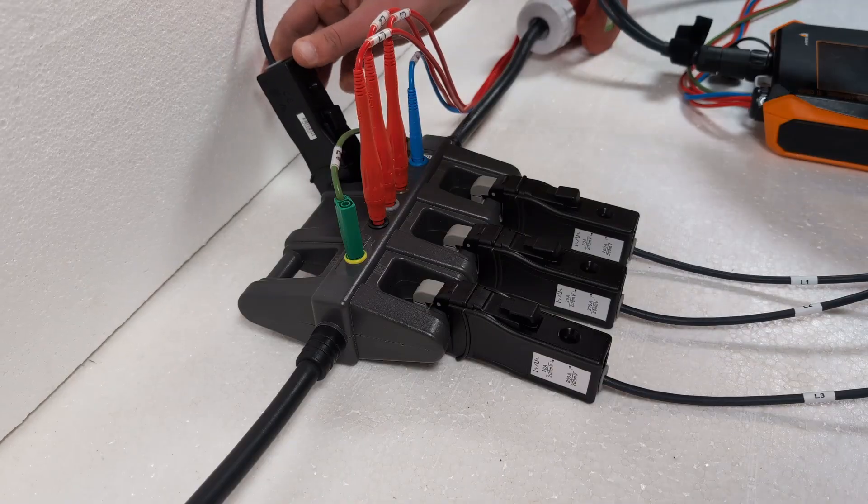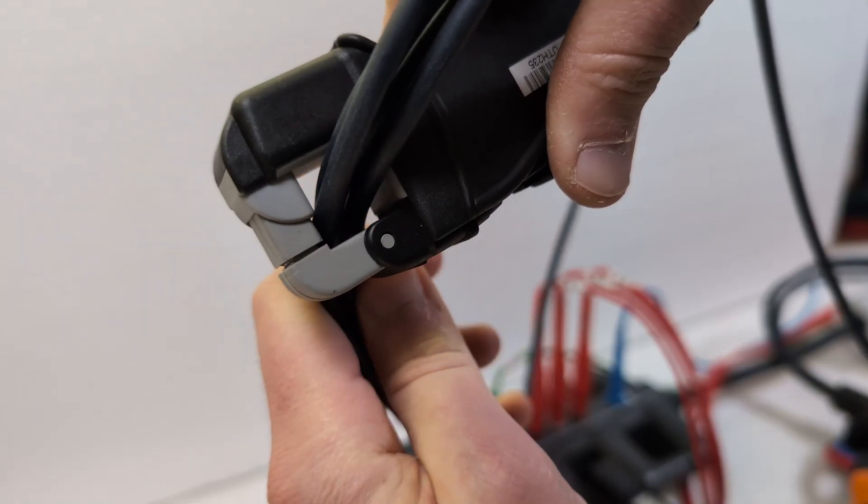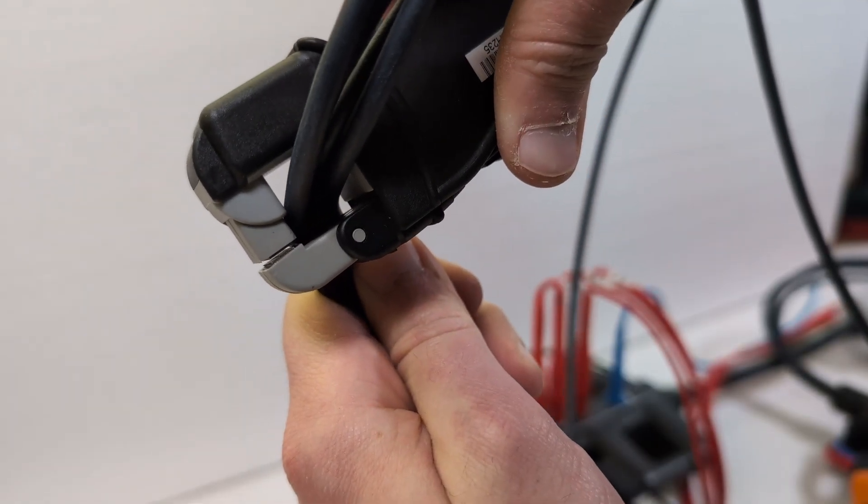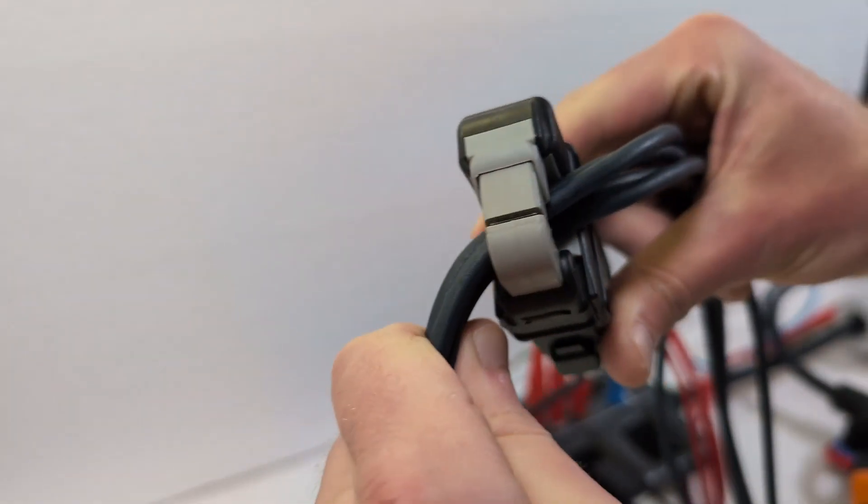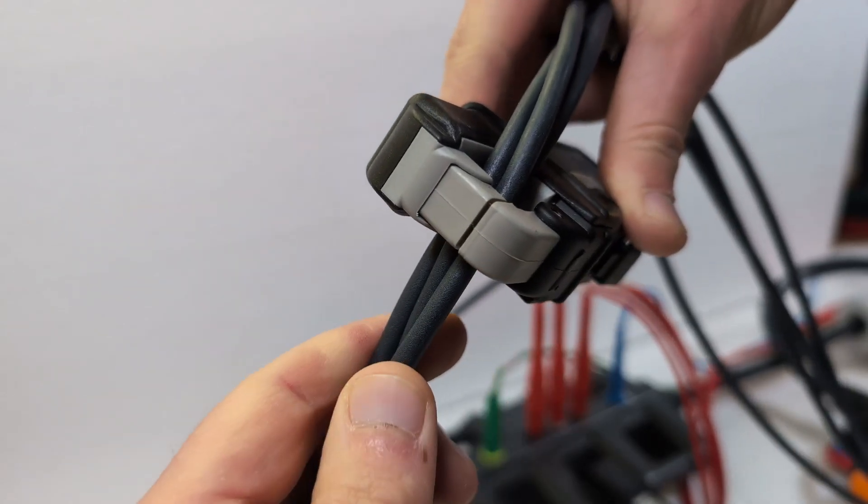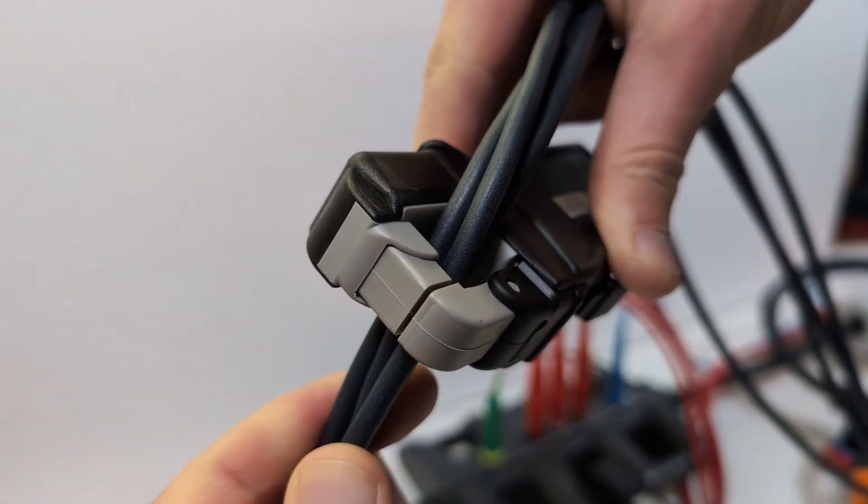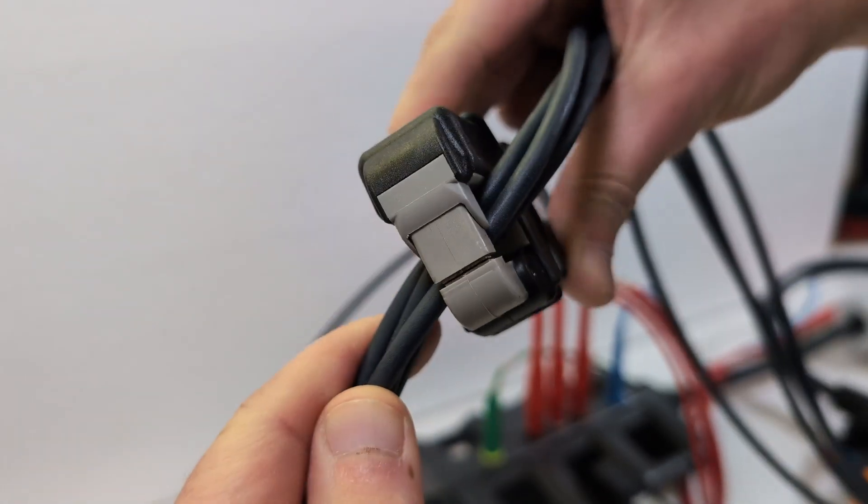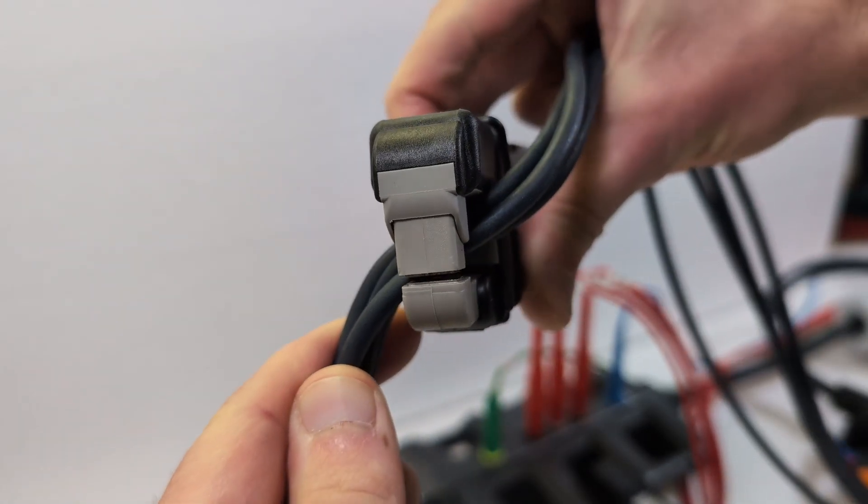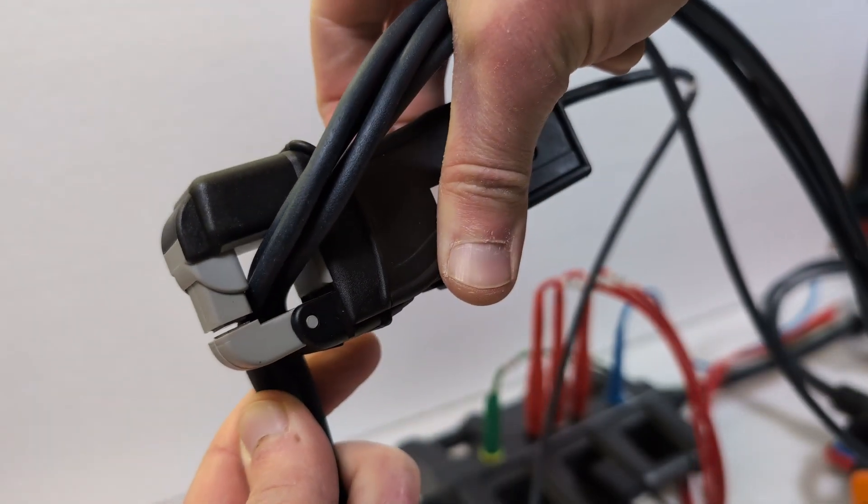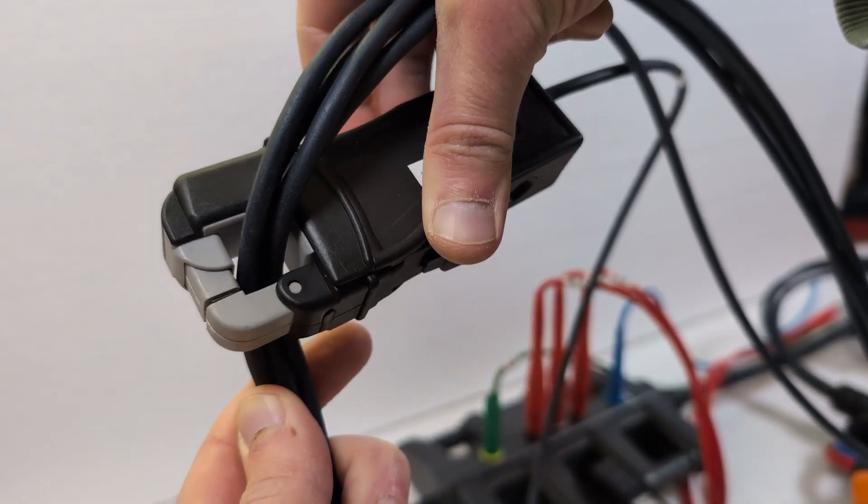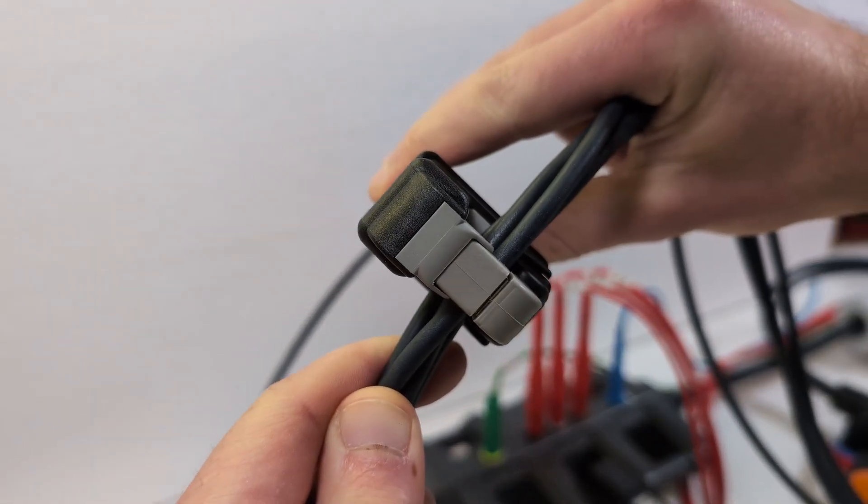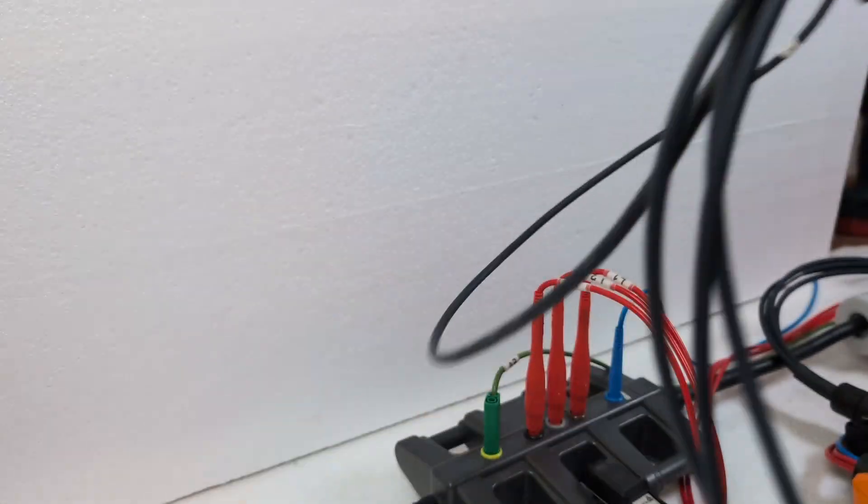Even if there is not much space available, you should ensure that the current clamps are not subjected to too much mechanical stress and are completely closed. This is because a small air gap can lead to a large measurement error.